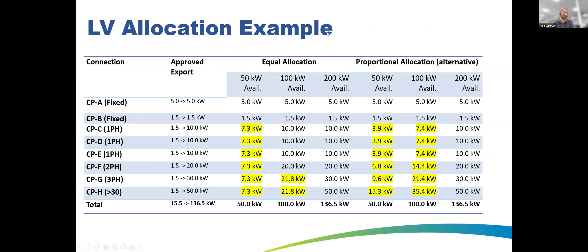As an example for a heavily overloaded transformer under equal allocation, everyone gets limited to 7.3 kW, except existing fixed connections which keep their 5 or 1.5 kW contract limit. As capacity opens up, more customers become unrestricted. Under proportional allocation, all customers are restricted simultaneously but larger systems get more.